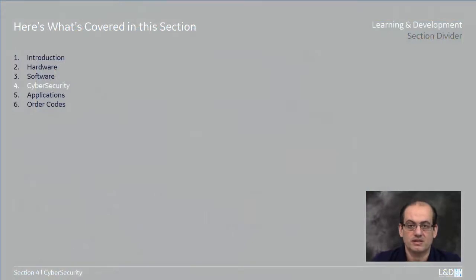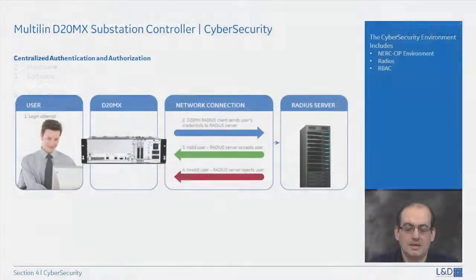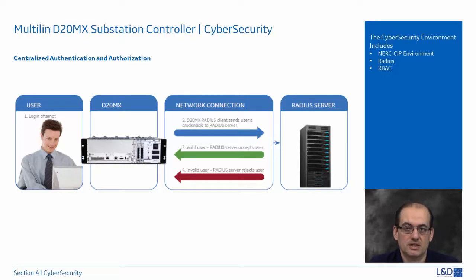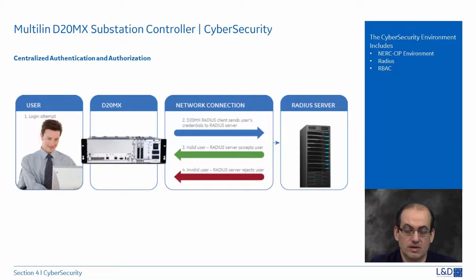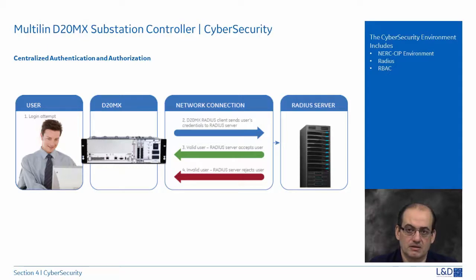In this section we will discuss the added value of cybersecurity in the D20MX. The D20MX supports role-based access control for both online and offline scenarios. When the RADIUS server is online and a user tries to access the D20MX, the device sends the credentials to the RADIUS server over encrypted communication, and the server replies whether the user is valid and grants access only to permitted areas — enabling centralized management of all D20MX devices in the field. Offline passwords can also be encrypted and updated via a Vault application.